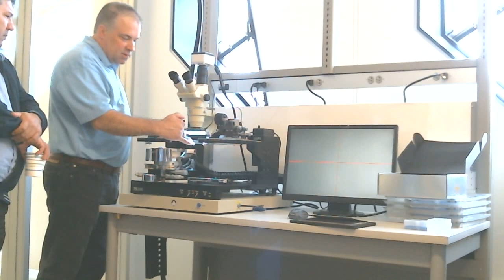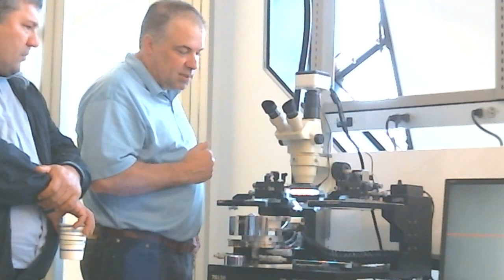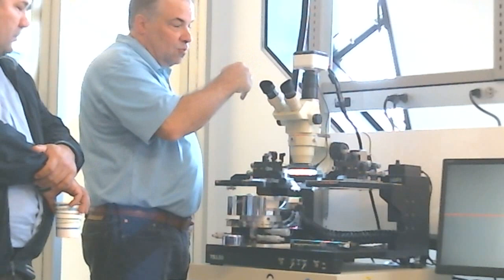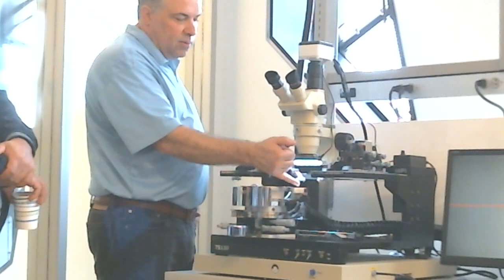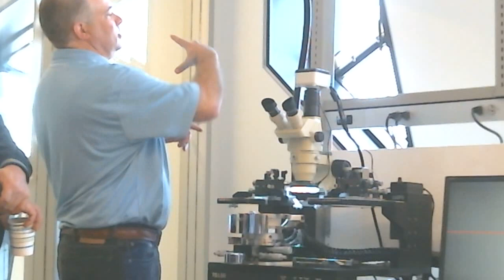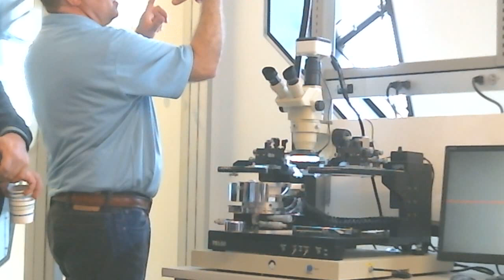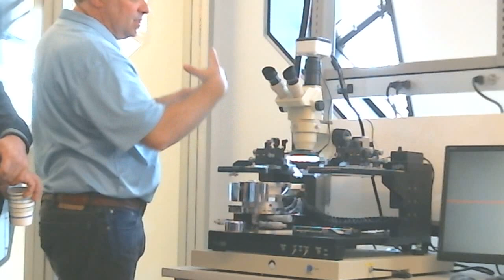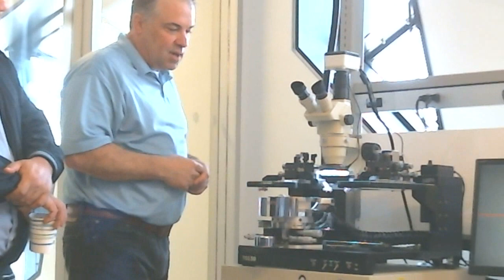These are ceramic, designed for electrical insulation. They won't get any grounding, noise, or influence from the chuck itself or the aux chuck. In the back right corner of each ceramic aux chuck there's what we call a fence. The idea is you take your substrate and bank it up against this fence - place your die or calibration substrate down flat on the ceramic, then push it into the corner where the fences are.